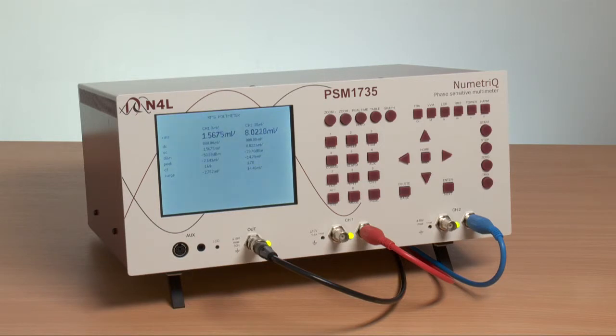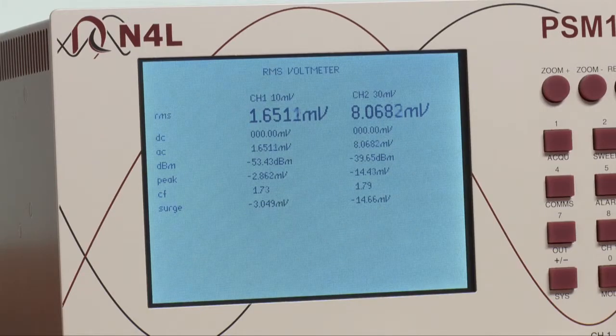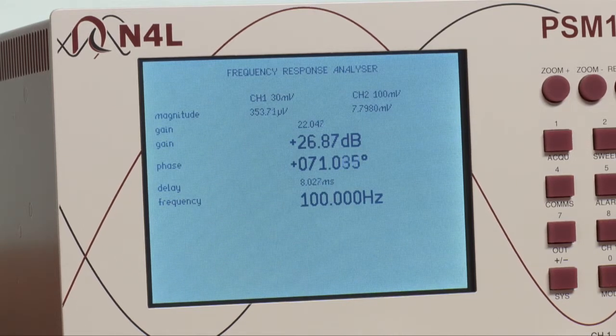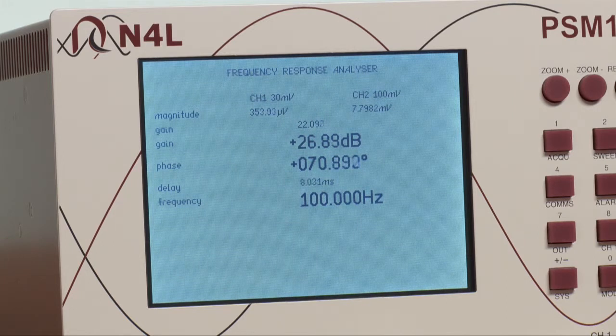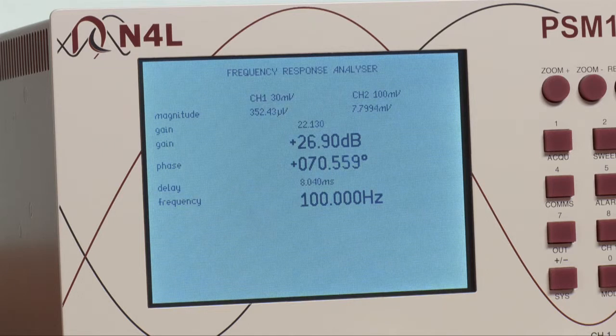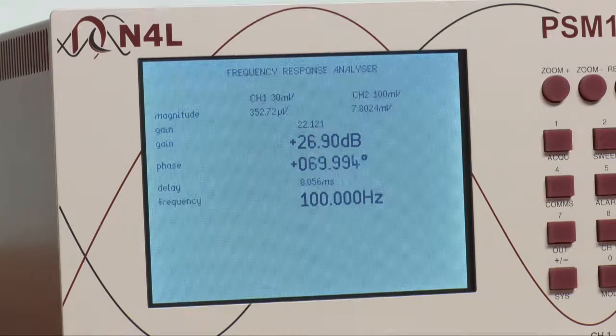If we now go to FRA mode, we can see that we have gain of 26 dB with 71 degrees phase angle at the injected frequency, which happens to be 100 Hz. This injection frequency can be changed during a sweep. But what we want to illustrate is that the gain phase plot is dependent not only on the frequency and injection signal level, but also the load of the power supply.